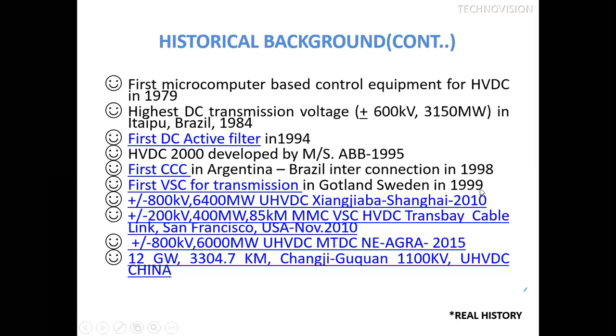This was the first step towards the new, modern technology in the field of HVDC in 1999. That was based on voltage source converters, that is, IGBTs. Otherwise, up to 1998, we were using thyristor technology in the world, and later on, we started development in voltage source converter technology. Later on, China developed plus minus 800 kV, 6,400 megawatt ultra high voltage DC in 2010. So that was one of the records by them.